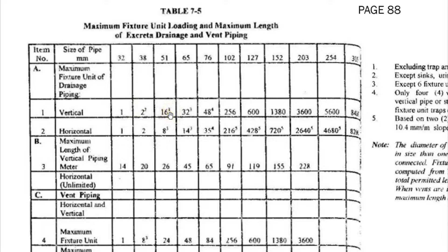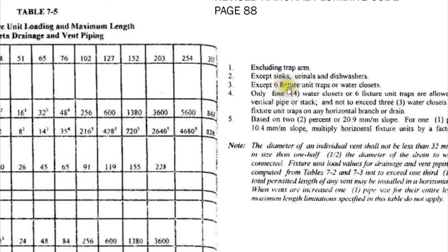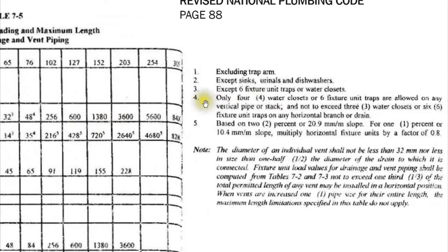The value 16 has a superscript of 3. Note number 3 says: except six fixture unit traps or water closets. So if you have a water closet connected to your vertical pipe, do not adapt 16 — move to the next higher value. Similarly, 32 also has superscript 3, so move to 48. The value 48 has superscript 4. According to note number 4, only four water closets or six fixture unit traps are allowed on any vertical pipe or stack. If you have five or more water closets on the vertical pipe, move to the next higher value.